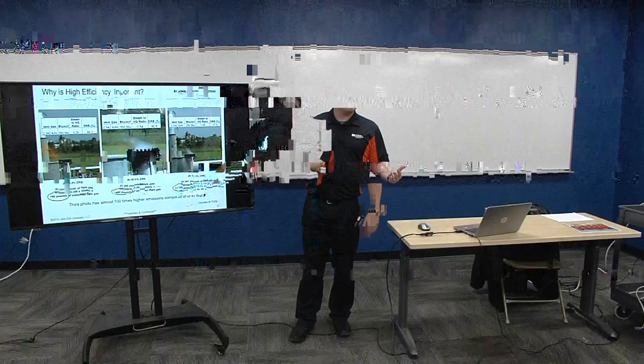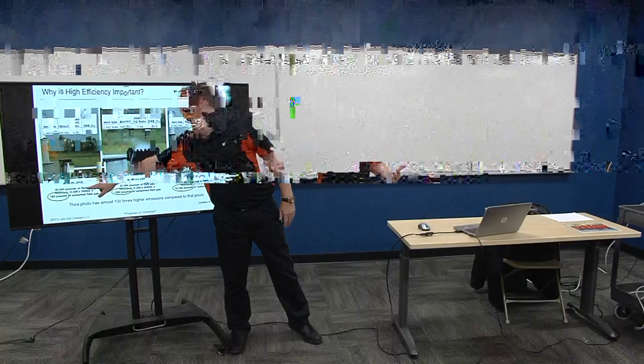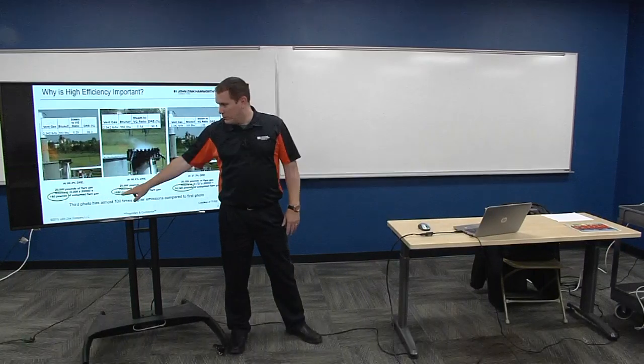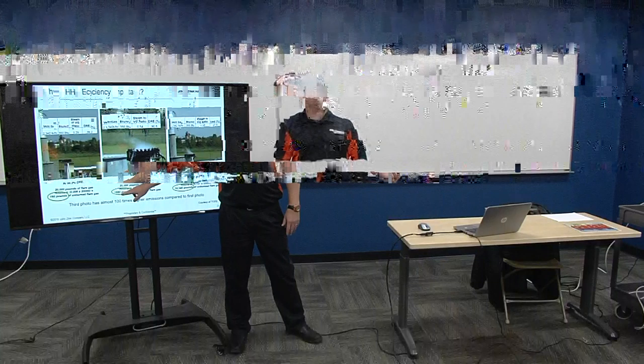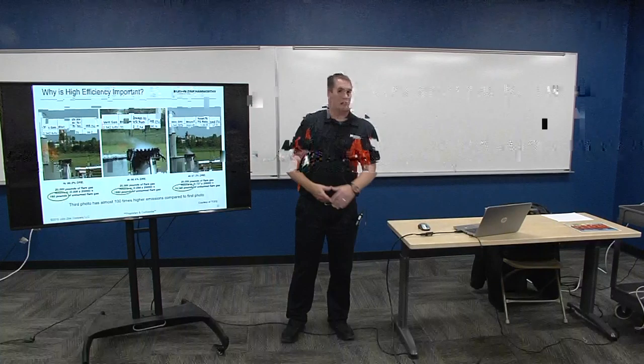So if you look at the unburned hydrocarbons of that 20,000 pounds of flare gas, in the correct operating philosophy, that's 160 pounds. Well, when you increase it just a little bit, you go a little more than 10 times the amount of unburned hydrocarbons being released to the atmosphere. And it gets even way worse if you oversteam.